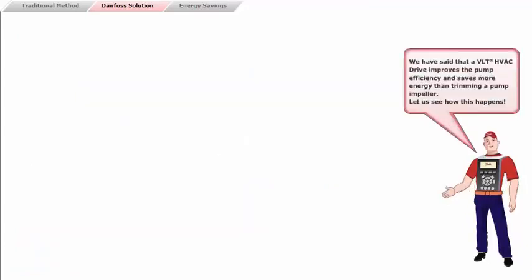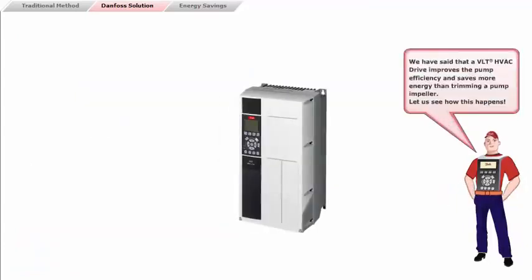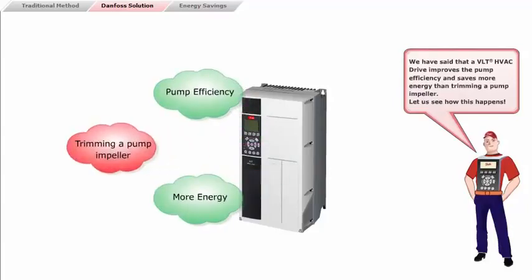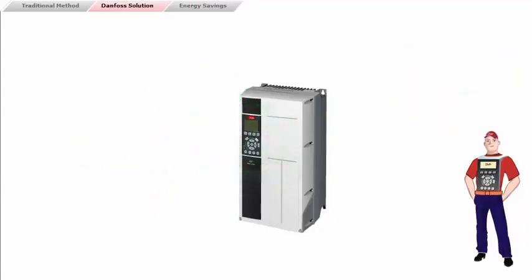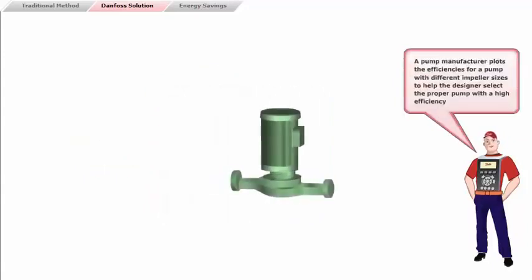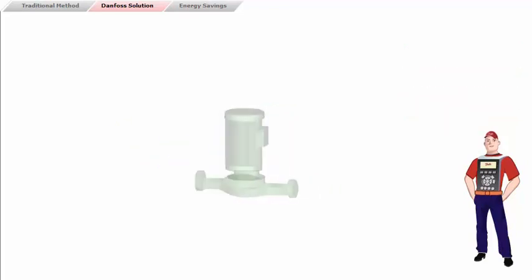We have said that a VLT HVAC drive improves the pump efficiency and saves more energy than trimming a pump impeller. Let us see how this happens. A pump manufacturer plots the efficiencies for a pump with different impeller sizes to help the designer select the proper pump with a high efficiency.